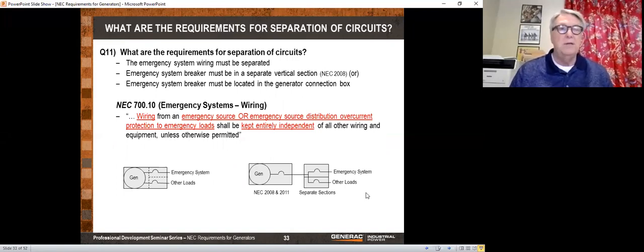Question 11, this is separation of circuits, and I'm not going to get into this too much, but it used to be if you have one generator, but it supplies emergency loads and non-emergency loads, then you put two circuit breakers on the generator. And those two circuit breakers, you have to have two transfer switches, one for emergency and one for other. That's part of the code. And they have to have their own circuit breakers. Well, it used to be that we just put two circuit breakers together. Then the code came out and said, nope, we are not going to allow that.